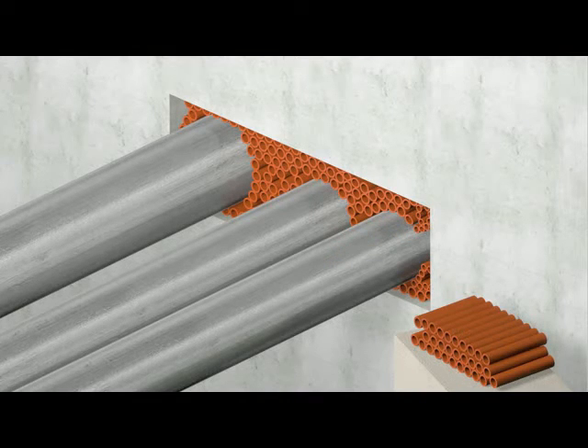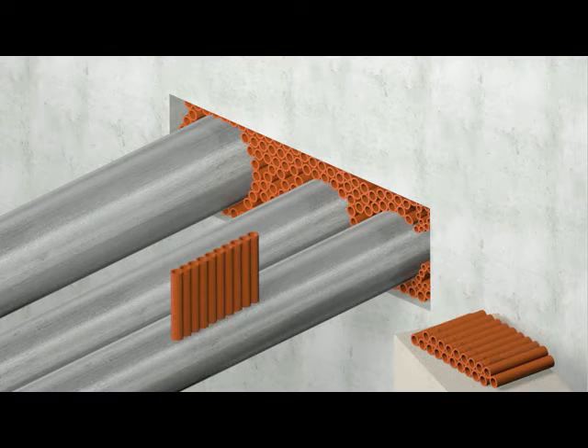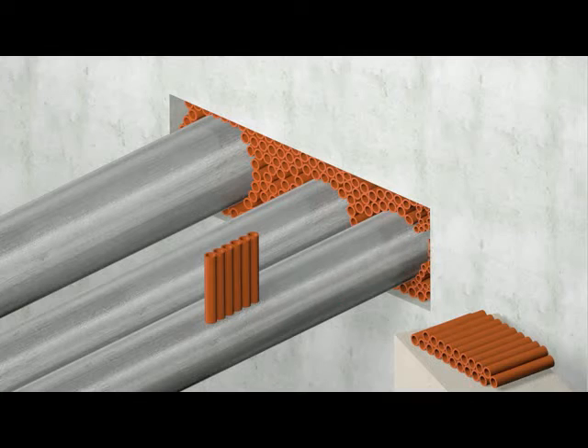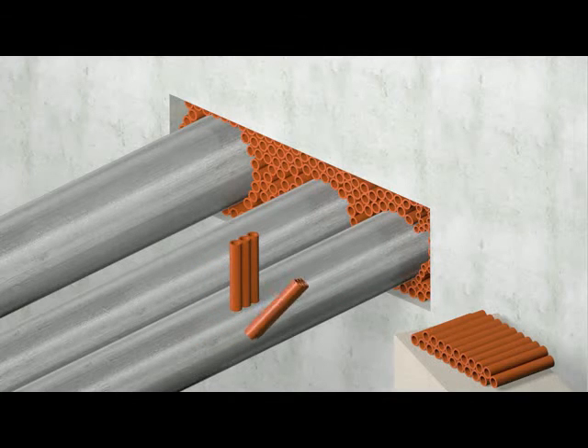The smaller openings are now filled with parts of the sets of multi-filler sleeves. To tear off sleeves from the multi-set, the procedure is to do this backwards-forwards and not sidewards. This is because of the strength of the intermediate rubber parts.